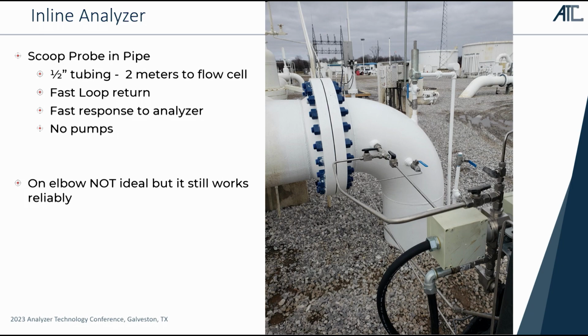So here's one. Actually, it's not my favorite installation, because these guys put it right in on the elbow of a pipe, but this is an NGL pipeline, and they put the probe into the side of the pipe. They're running a fast loop out. The fast loop is running over here, running over to a JP3 infrared analyzer, comes straight out of the JP3 infrared analyzer, goes right back into the pipe. So now they have continuous flow through that flow cell, and it's being driven just by the velocity in the pipeline.